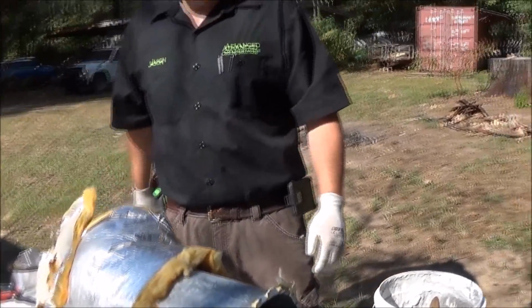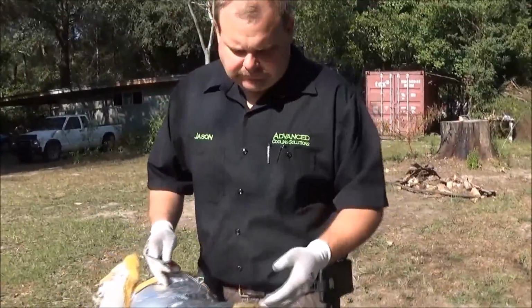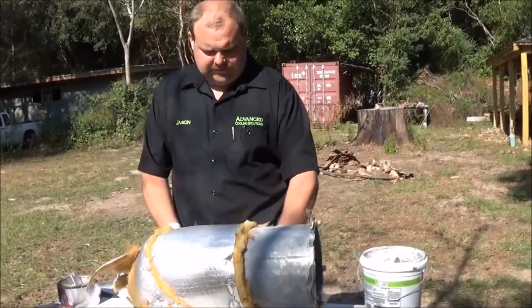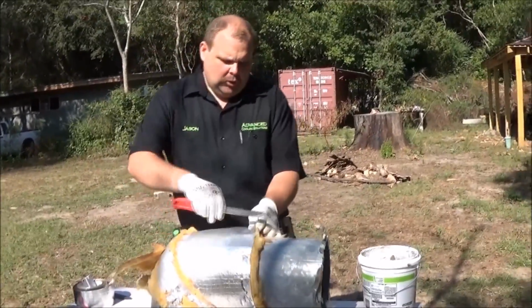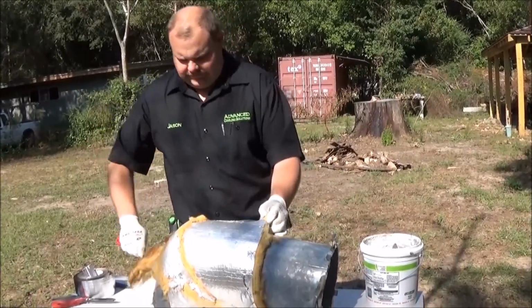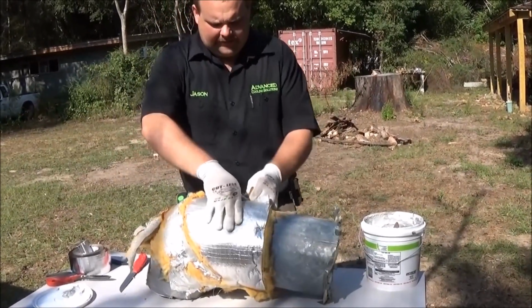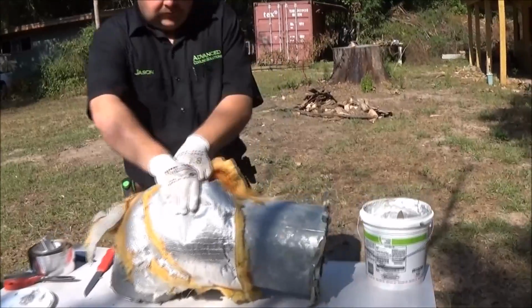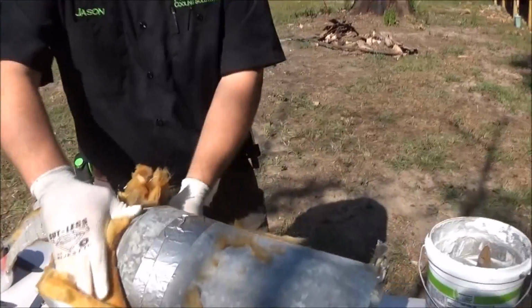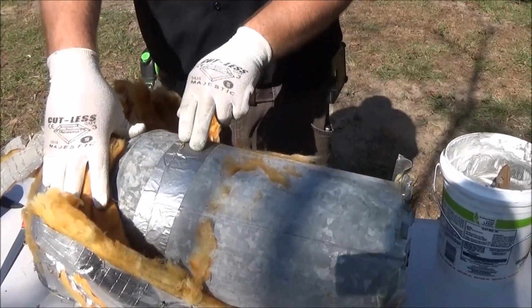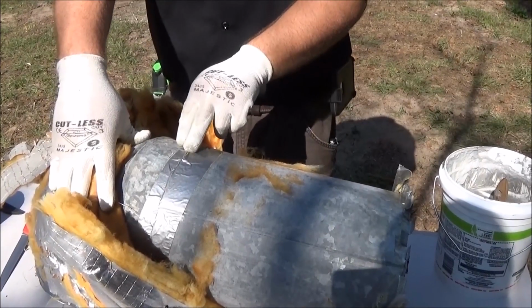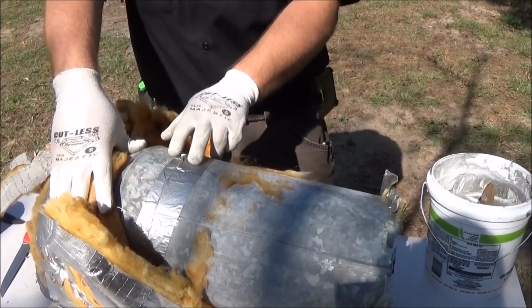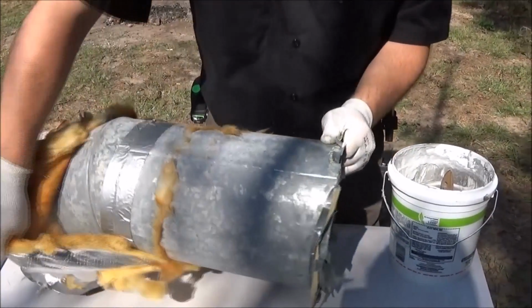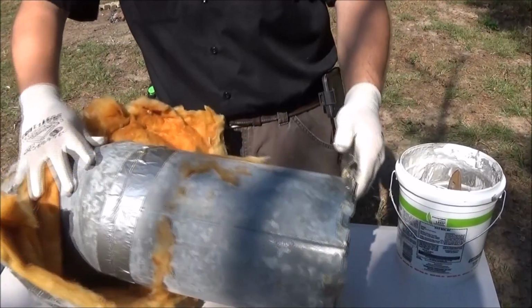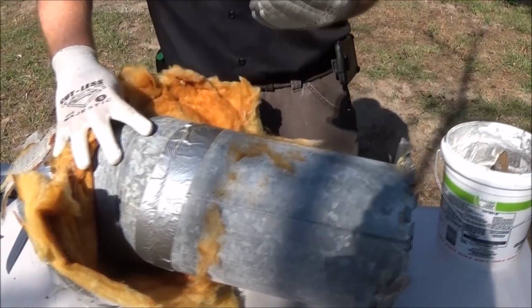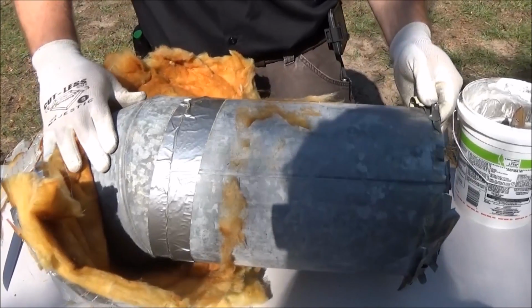So what we did up in the attic is take the ductwork that was fixed up there and cut off the old insulation. We peeled it back, and when we did, we saw that it had duct tape, which is not code approved for this particular seam. You can also see how it's loose on there. Even though it is there, it's not providing that airtight seal that we look for.